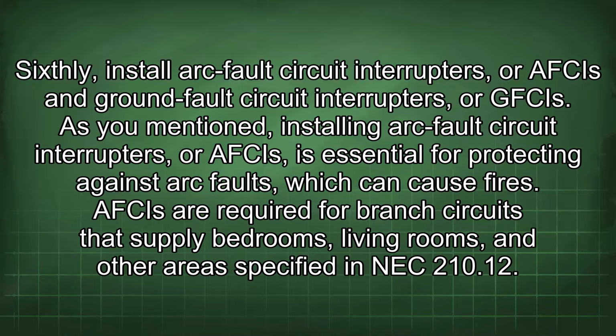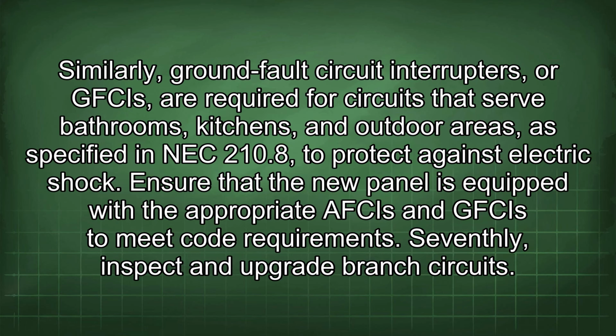Sixthly, install arc fault circuit interrupters, or AFCIs, and ground fault circuit interrupters, or GFCIs. As you mentioned, installing AFCIs is essential for protecting against arc faults, which can cause fires. AFCIs are required for branch circuits that supply bedrooms, living rooms, and other areas specified in NEC 210.12. Similarly, GFCIs are required for circuits that serve bathrooms, kitchens, and outdoor areas, as specified in NEC 210.8 to protect against electric shock. Ensure that the new panel is equipped with the appropriate AFCIs and GFCIs to meet code requirements.